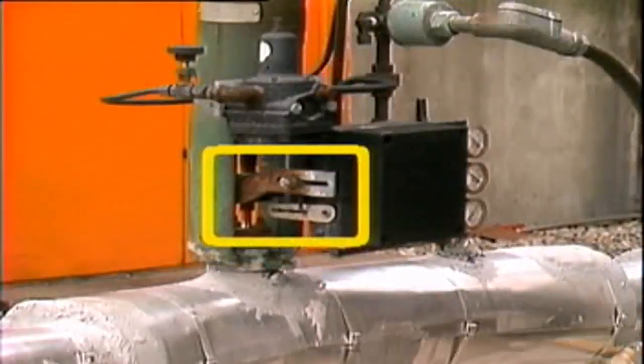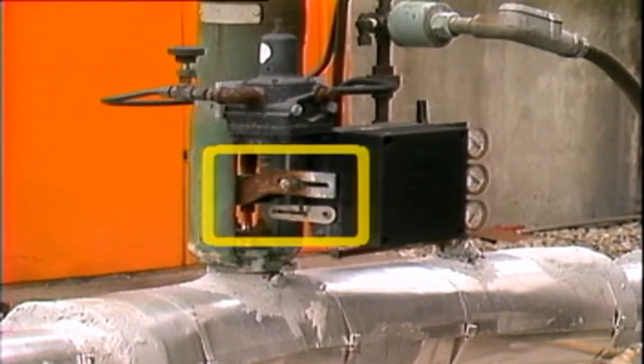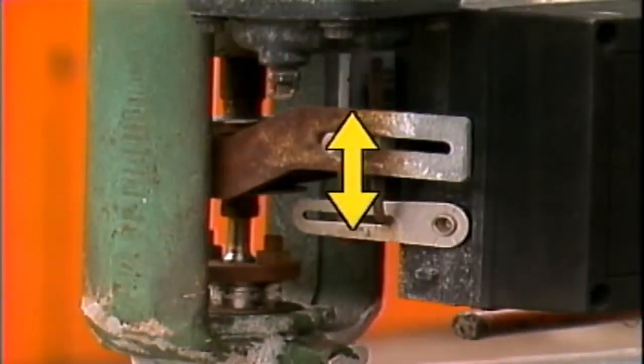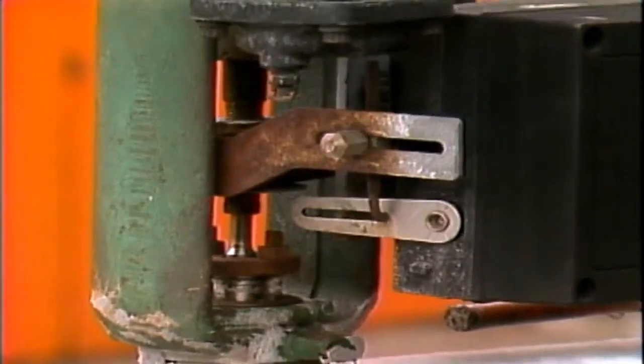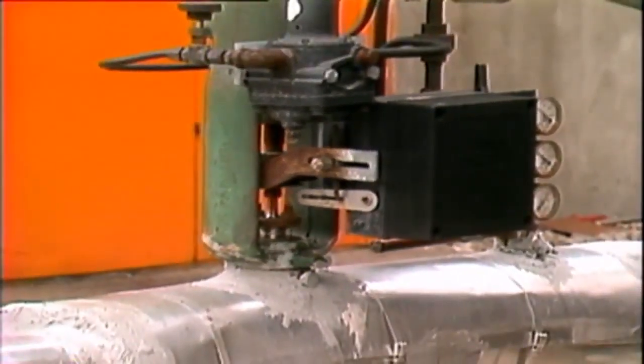A mechanical linkage joins the actuator stem to the positioner. This mechanical linkage may also be called a feedback linkage. As the actuator stem moves up or down, it also moves the linkage.